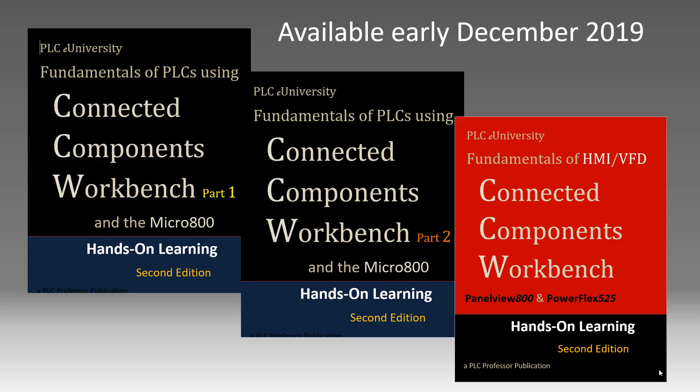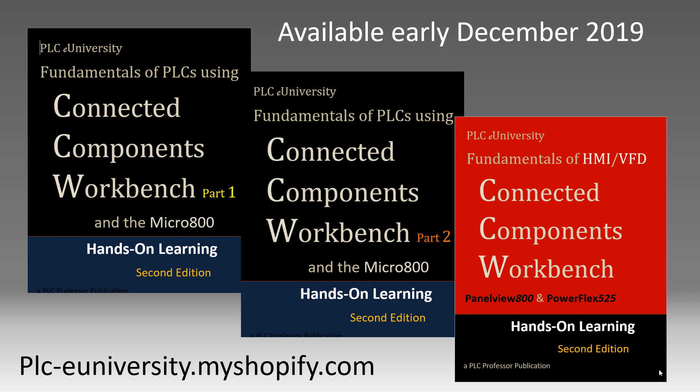We'll go to diagnose, fault, clear fault. If your simulator faults, go to micro 850, fault diagnostics, and you can clear the fault by clicking here. What I was doing was re-downloading the whole program to get it back in the unfaulted condition. This is a little bit quicker, but you have to be online to do it. So if you're going to work with these manuals, they will be available in early December 2019 from PLC eUniversity at myshopify.com.